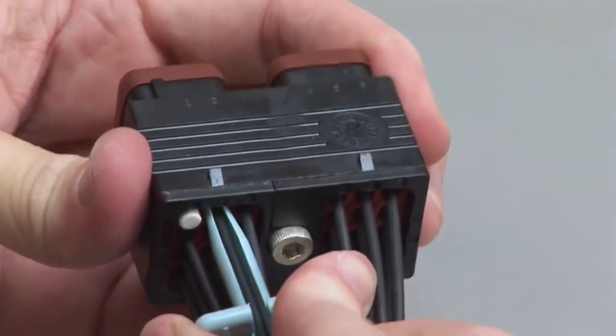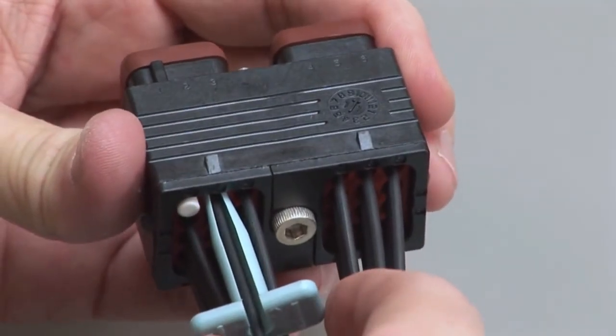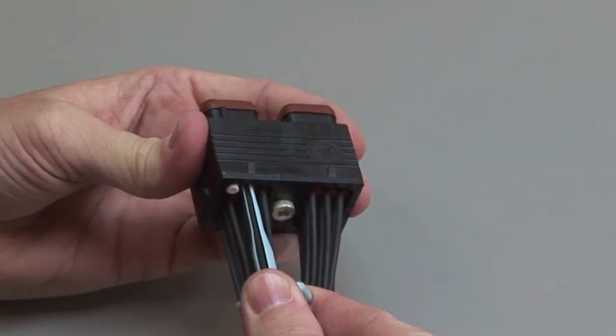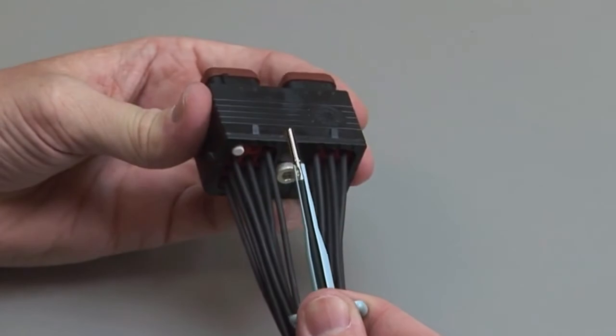Slide the tool along the wire into the cavity until it engages the contact and resistance is felt. Make sure you keep the tool straight and do not twist or angle the removal tool. Pull the contact and wire assembly out of the connector.